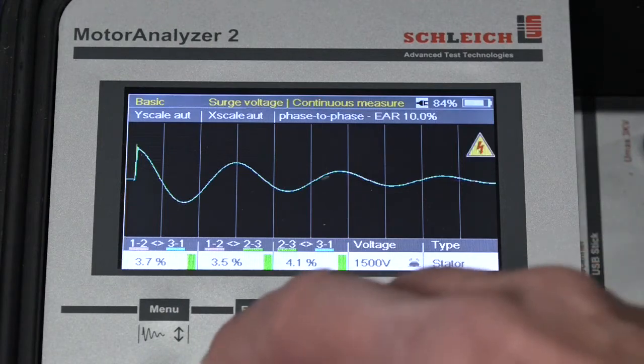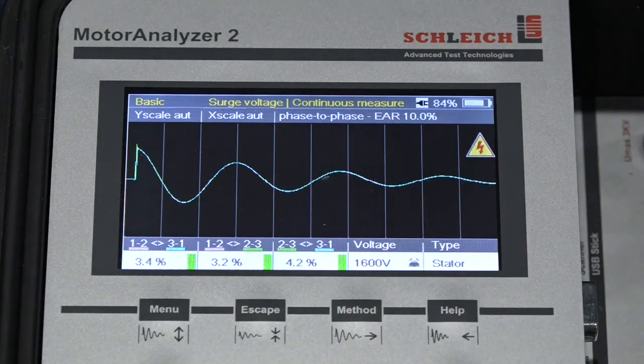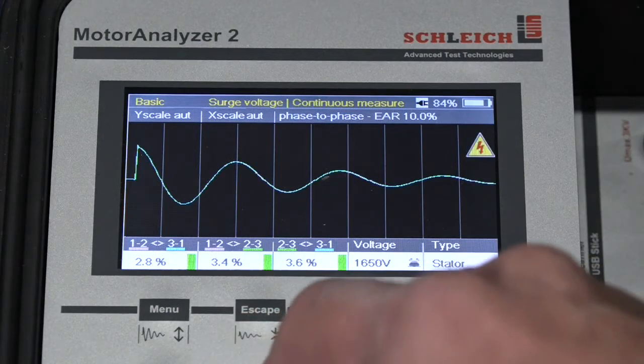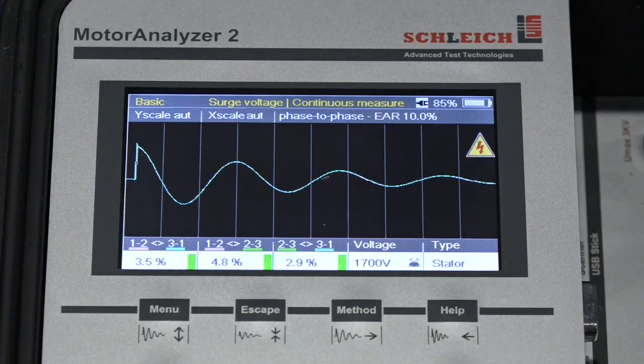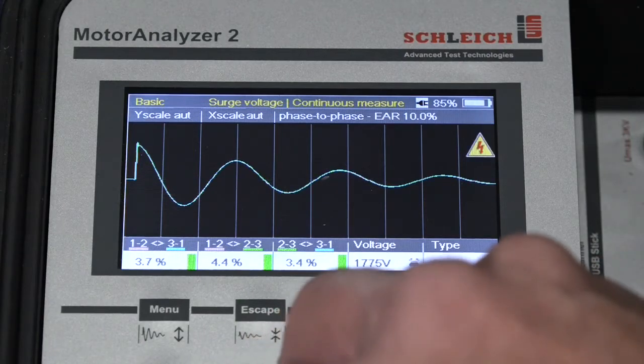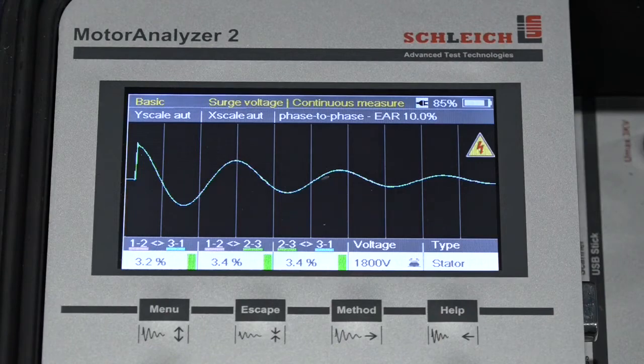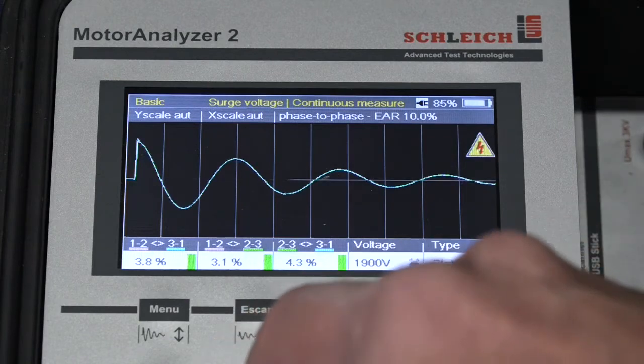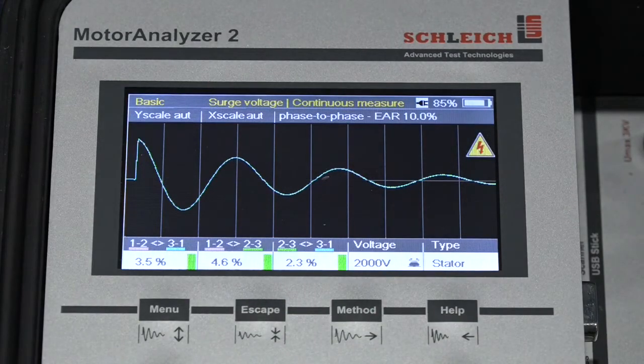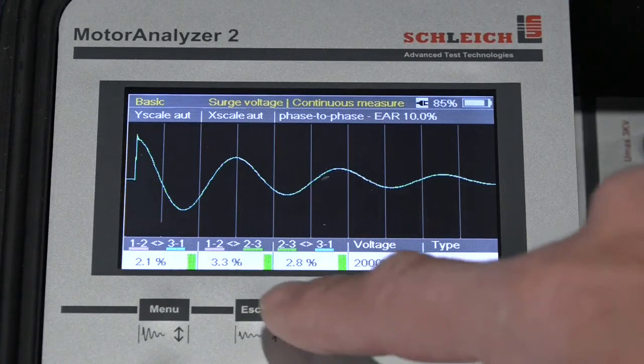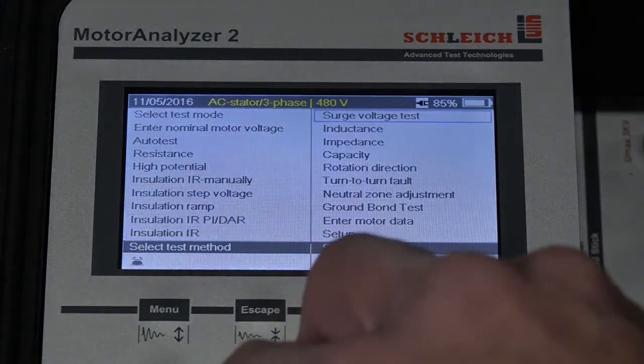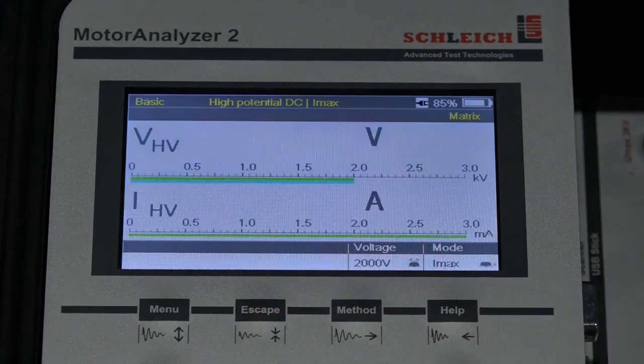1500 volts. 1600 volts. 1700 volts, 1800 volts, 1900 volts, and finally 2000 volts. And I'll press the stop button to end the test. So here what we've done, we've disconnected our stator and just did a simple surge test on the windings. Let's back out of this and do a high potential test, a DC high pot test.